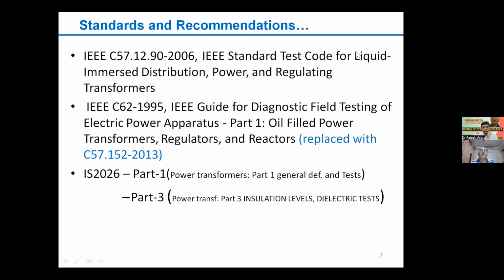So C57.12.90-2006 is the standard test code for liquid-filled or liquid-immersed distribution, power and regulating transformers. And C57.62-1995, which is now replaced with C57.152-2013, is basically a guide for diagnostic field testing of power transformers. Both are exhaustive documents, and it depends upon the different utilities, their practices, how they test, their capabilities, and how much infrastructure they have developed according to their resources, what tests they should perform. Accordingly, the practice may vary in different utilities.